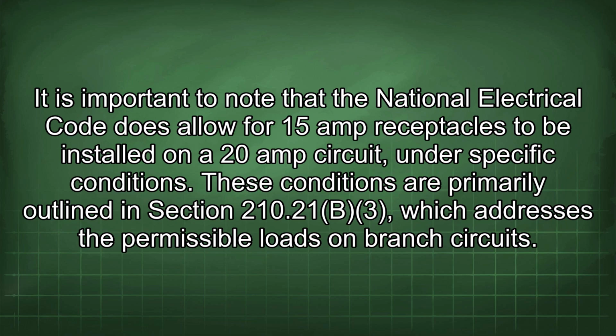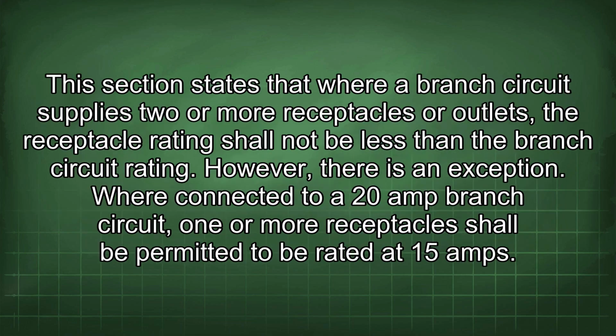These conditions are primarily outlined in section 210.21(B)(3), which addresses the permissible loads on branch circuits. This section states that where a branch circuit supplies 2 or more receptacles or outlets, the receptacle rating shall not be less than the branch circuit rating. However, there is an exception. Where connected to a 20-amp branch circuit, 1 or more receptacles shall be permitted to be rated at 15 amps.